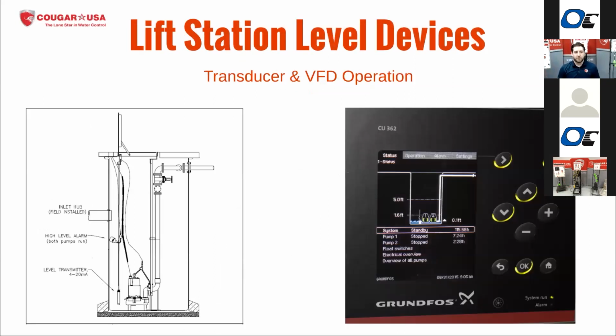So the other alternative to using float switches for level indication in the pit is to use a submersible transducer. In this case, we're going to have our pressure sensor down towards the bottom of the pit, and it is going to be reading the pressure, the weight of the water in the pit, and giving that signal over to our controller, which is then going to convert it to a height in feet. And what this is going to do is allow us to set the on and off points for all of the pumps and the alarms based on the height in the basin and not by individual points for the float switches. So we have continuous readout of the level.